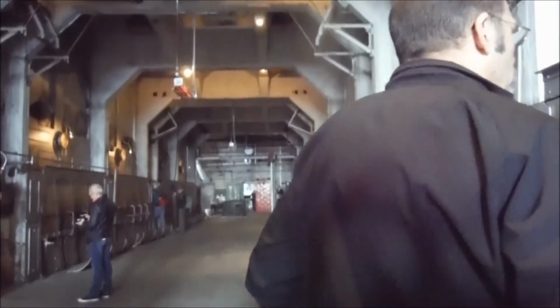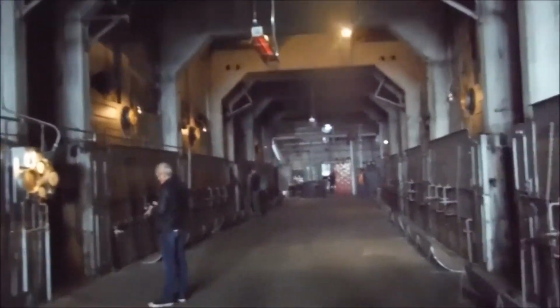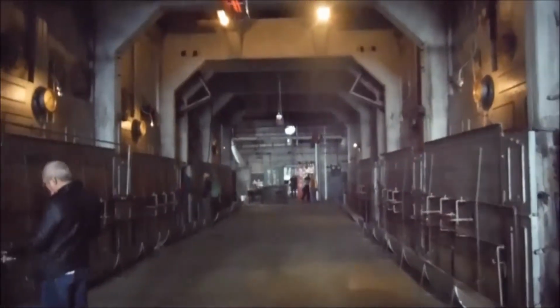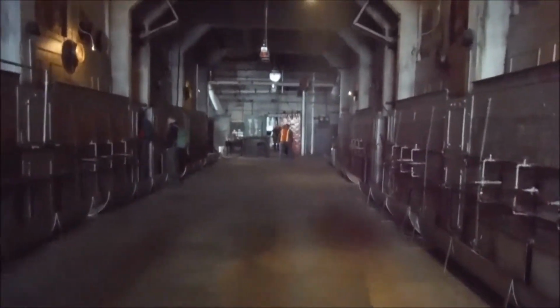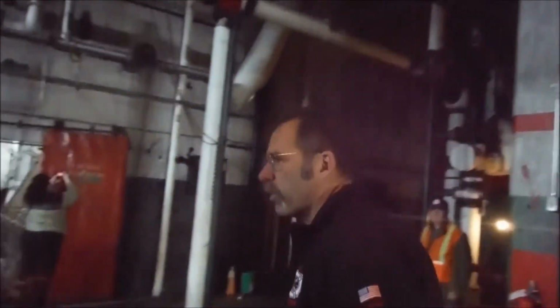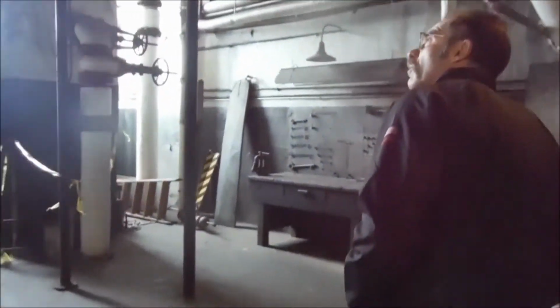Somewhere probably up on the catwalks on the upper level where we aren't and where we can't get would be some fairly elaborate and detailed water level measuring and monitoring devices. Maybe as simple as sight glasses, maybe as complicated as having some automatic shut-off feature. Because high water, in which if the water level gets too high, you carry water out with the steam and dump it into your turbines, that's a bad day. Or low water, where the generating tubes are no longer kept full of water and you overheat. Both are like the two most catastrophic things you can do to a boiler. Yes. That stuff must be on the upper level, but we can't get to it.